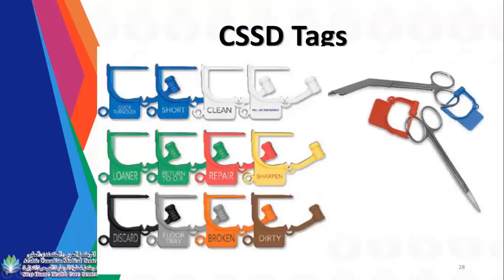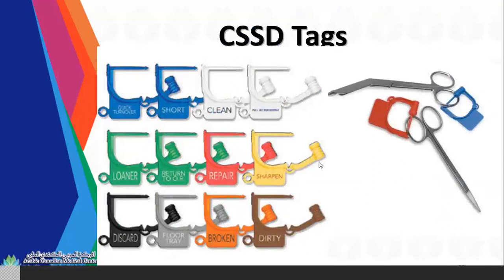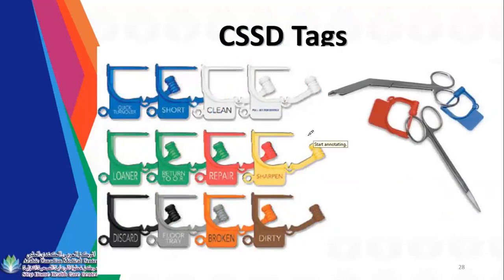So CSSD tags, there are different tags in CSSD. I'm not sure if it is clear. Sometimes you are not using this tag, which is clean, but it's okay. It depends on the facility. So when the instruments need to be sharpened, you need to put this label. The instruments need to be sharpened because they did not pass the quality check or functionality testing. For example, your small scissor should cut clean the yellow latex, and your large scissor can cut clean the red latex, or the orange rubber, which is your non-latex.